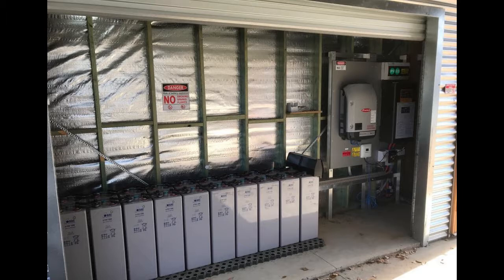Yeah, so it needs ventilation. It's definitely a requirement for lead acid batteries. So normally we'd recommend a Whirlybird on the roof, and behind the batteries along here, I think the customer's got like 4 or 5 vents down low. So there's a calculation that you do based on the battery capacity that tells you the size of the ventilation that's required.